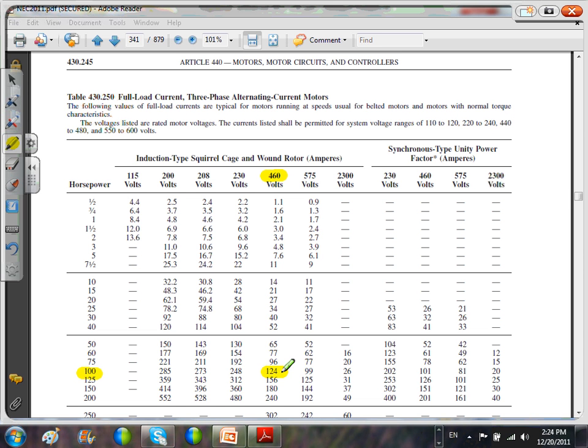So what do you do? You multiply it by 1.25 and you size the conductors. Multiply it by 1.15, size your disconnects. Also based on this, the horsepower and the voltage, you can size your magnetic starter. You can size the overcurrent protection device. If it's an inverse time circuit breaker, take this, multiply it by 2.5, size your inverse time circuit breaker. So this number becomes very, very important.